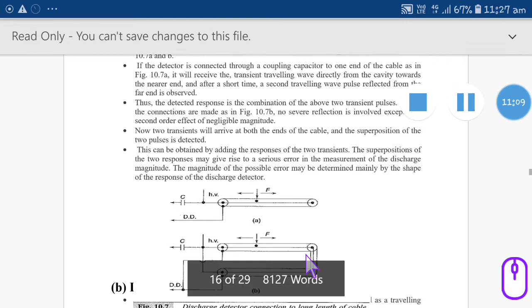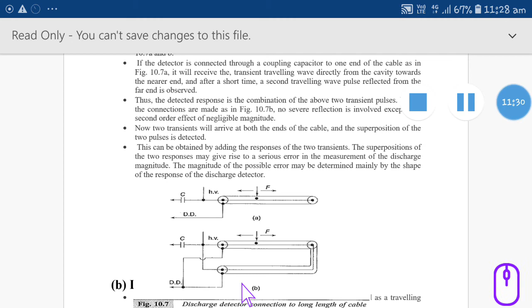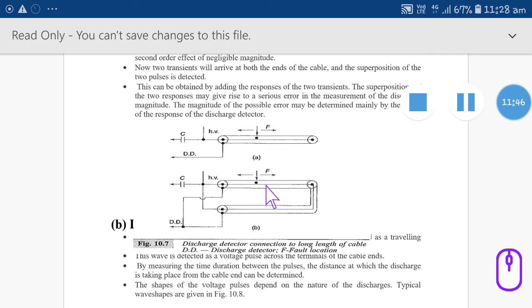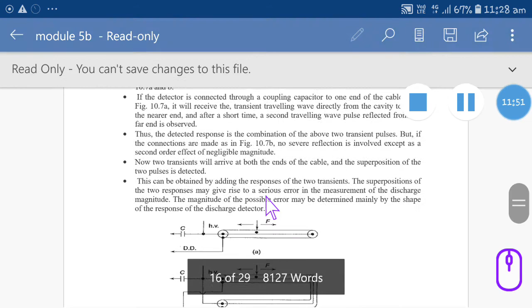Now two transient pulses take place. The detector response is the combination of two transient pulses, because another reflection takes place at the other end. Two transients arrive at both ends of the cable, and the superposition of the two pulses is detected. This can be expressed as the sum of two transient responses. This is the discharge detector for a long transient cable, as we analyze during testing of cables. We maintain the time duration between the pulses, and the distance of the discharge within the cable can be determined. This is partial discharge measurement.